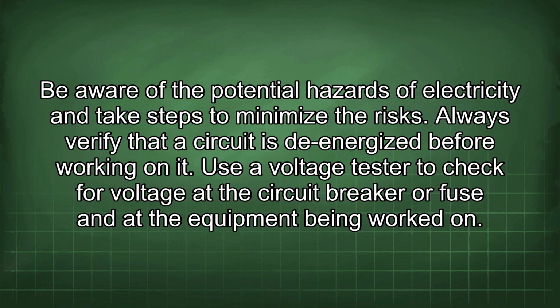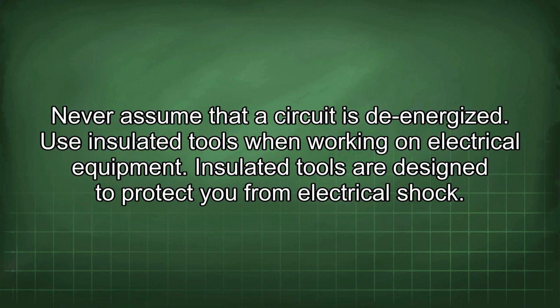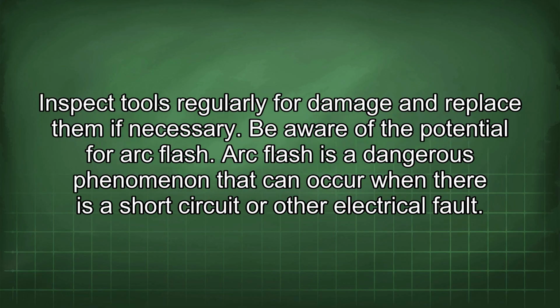Always verify that a circuit is de-energized before working on it. Use a voltage tester to check for voltage at the circuit breaker or fuse and at the equipment being worked on. Never assume that a circuit is de-energized. Use insulated tools when working on electrical equipment. Insulated tools are designed to protect you from electrical shock. Inspect tools regularly for damage and replace them if necessary.